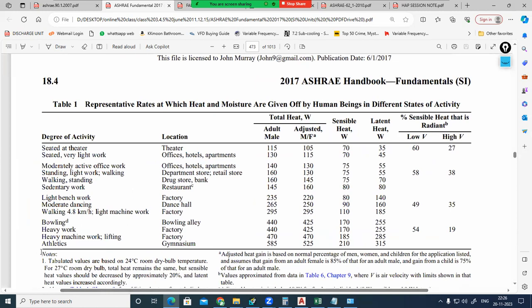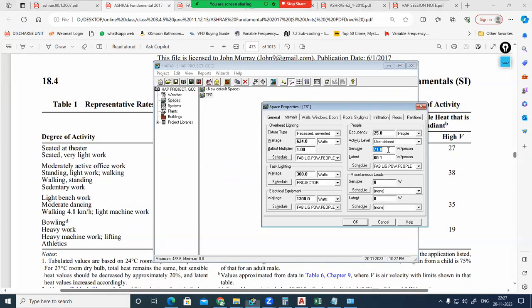But at the same time, if you are an athlete working at the gymnasium, the total heat gain will be 525. Out of 525, 210 sensible, 315 will be latent. Sensible less, latent more, because with respect to the activity, you will sweat more. So with respect to the type of activity, for example office, if you are doing moderately active office work, then you can consider 130 watt. Out of 130, 75 sensible, 55 latent. So you can come here. Okay, user defined: 75 sensible, 55 latent.